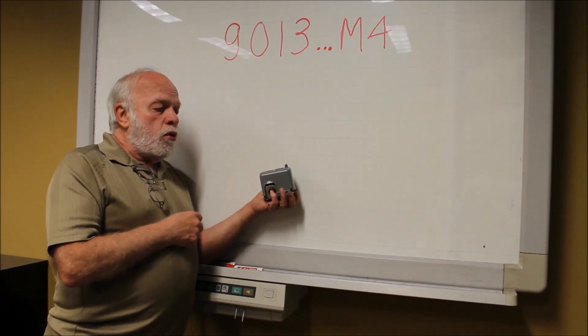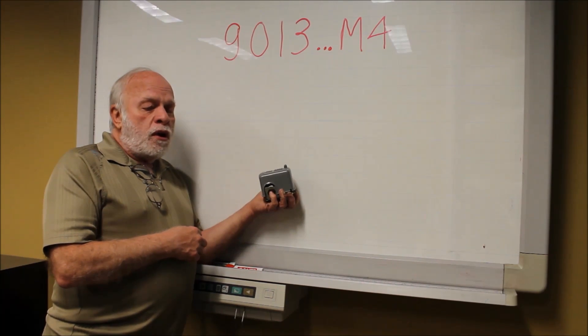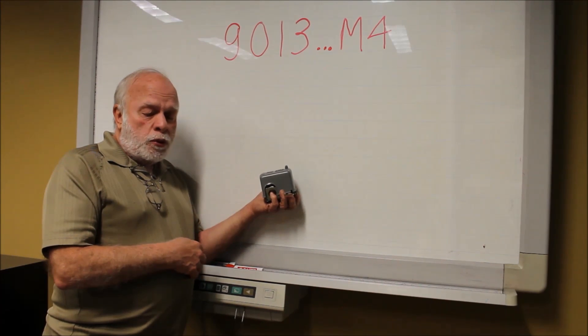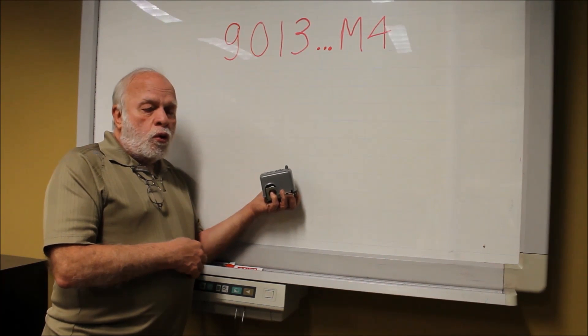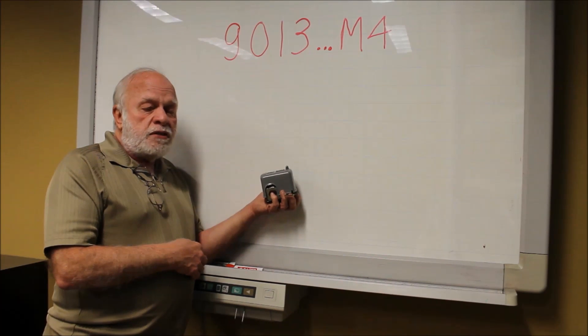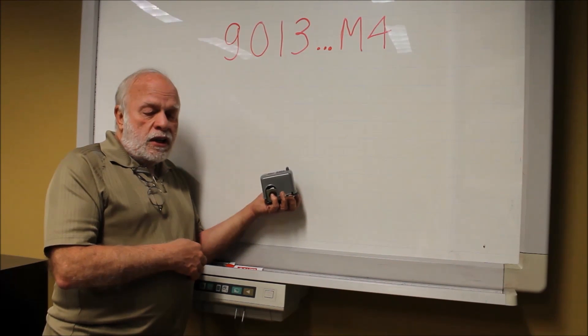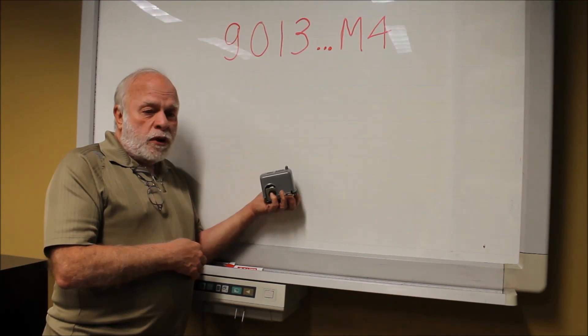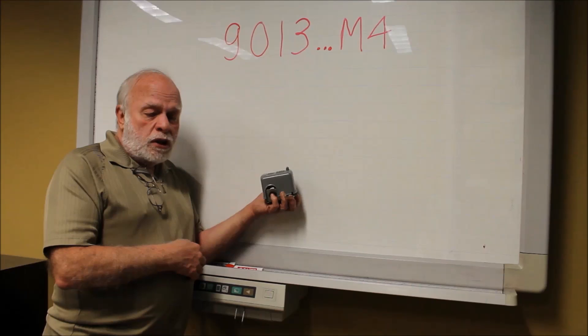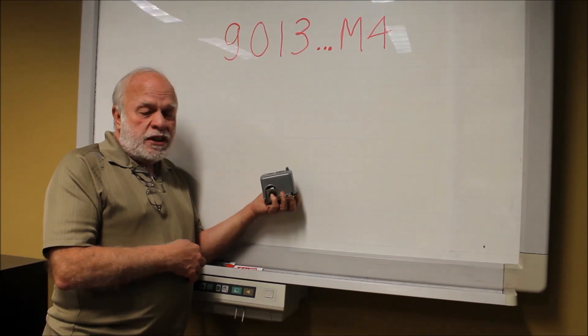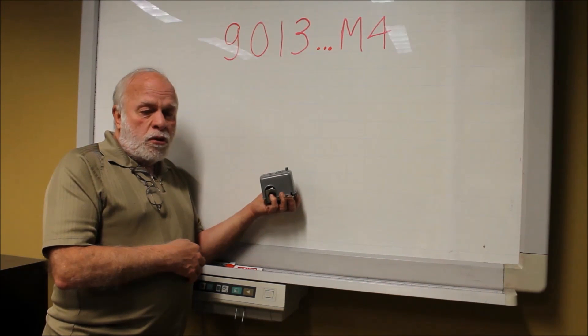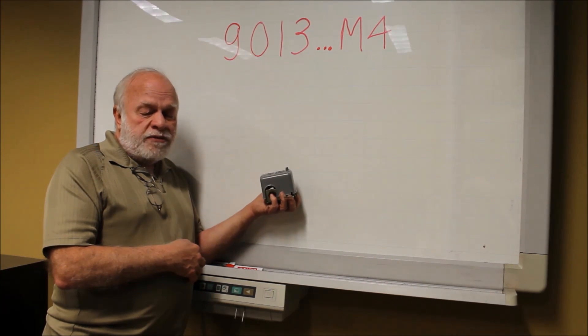The M4 is designed for wells that are slow producing or where a water source has relatively low incoming pressure. That incoming pressure could be too low and could cause a pump to cavitate and burn out. The M4 is designed to prevent that.